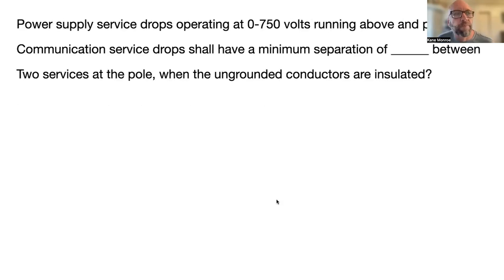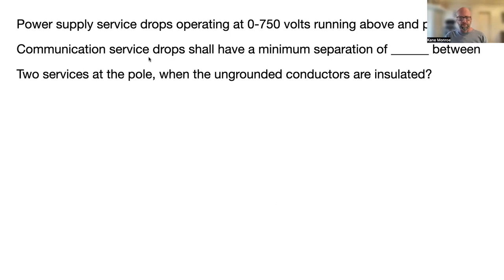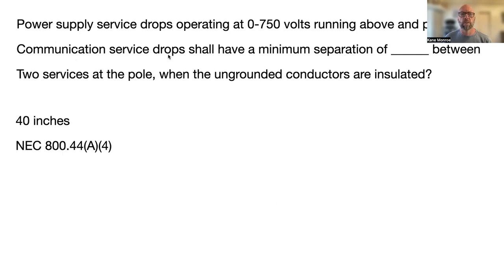Next question: power supply service drops operating at 0 to 750 volts running above and parallel to communication service drops shall have a minimum separation of blank between the two services at the pole when the ungrounded conductors are insulated. If you don't know the answer, go to the keyword index and look up 'communication service drops.' The answer is 40 inches — found at NEC 800.44(A)(4). Go ahead and highlight that.